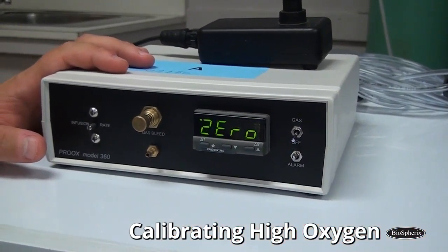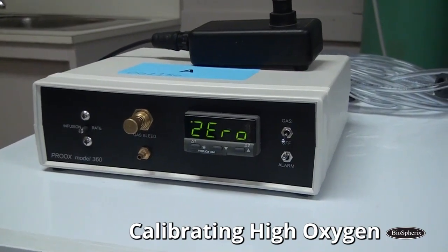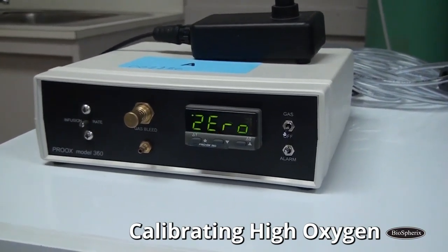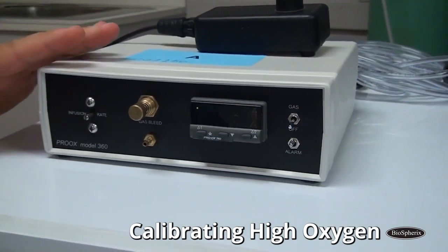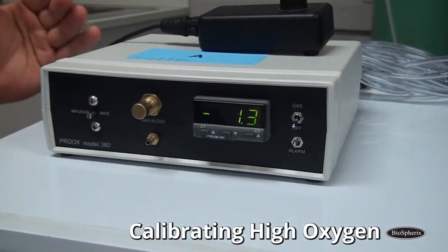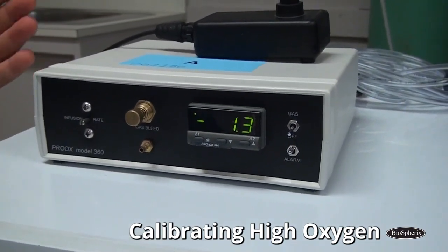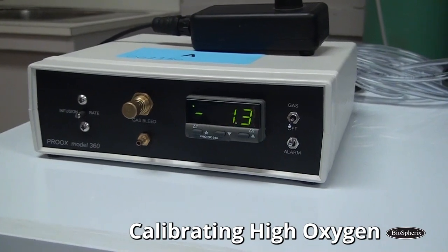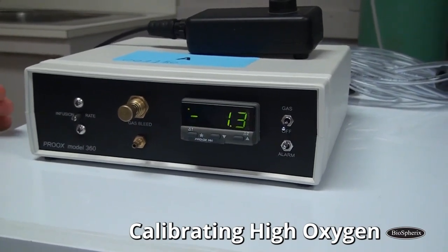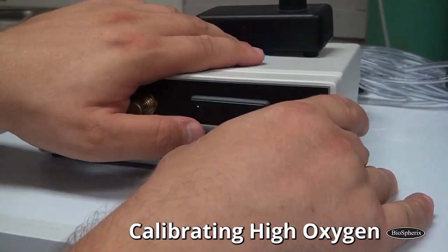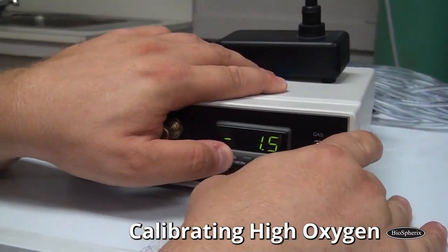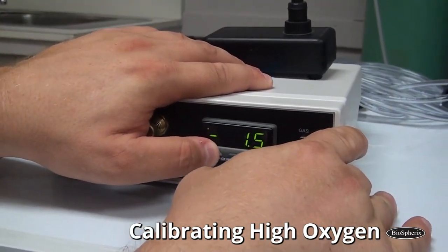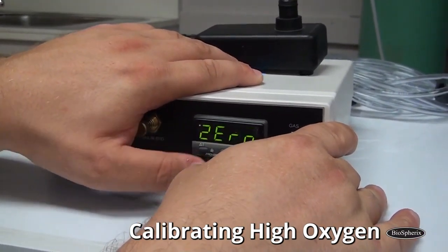And it's minus 1.3 is the coefficient. Again, the coefficient doesn't matter too much. What matters is what you do to that coefficient. So we were about 0.2 over from where we need to be. So I need to lower this by 0.2. So I hit the star and I press down twice while holding the star.